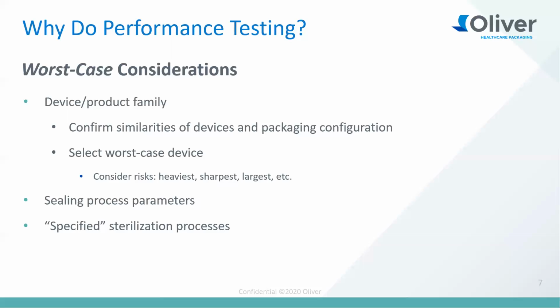You want to consider the risks there, the heaviest, sharpest, largest, et cetera. You sit through a risk assessment, and that's something we'll talk about a lot during this webinar, the risk assessment. A lot of this is based on risk, the decisions you make, and this is one of them for worst case. Also for the sealing process parameters, when you're sealing your packaging, whether it's a pouch or a tray, you do want to consider the worst case sealing process parameters for this performance testing. And that could be, and usually is, your OQ low settings, but sometimes it may be the nominal or high, depending on what kind of parameter set you have in the output. So you want to check your process validation and determine what settings to run at for this.